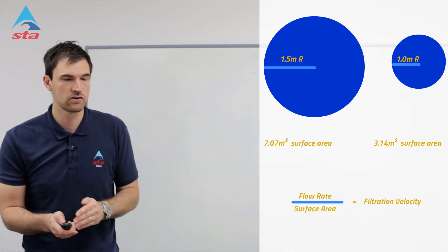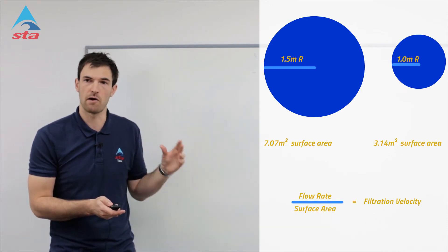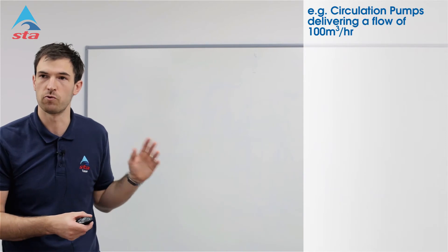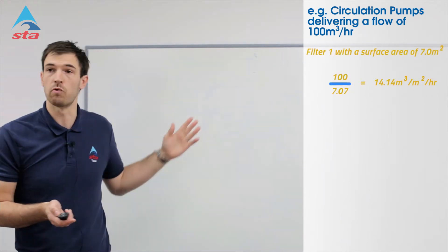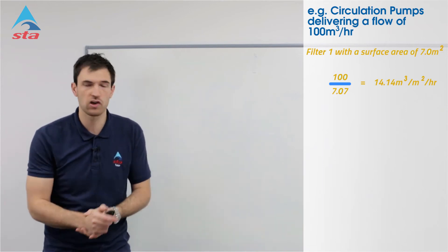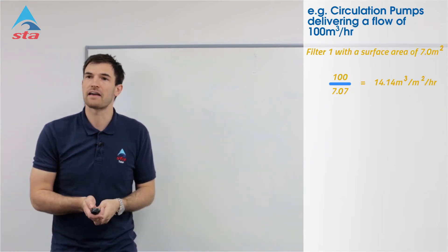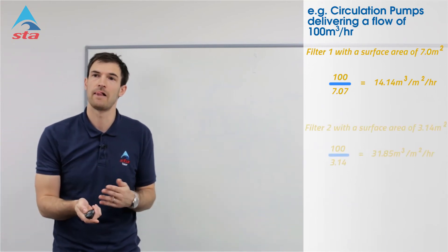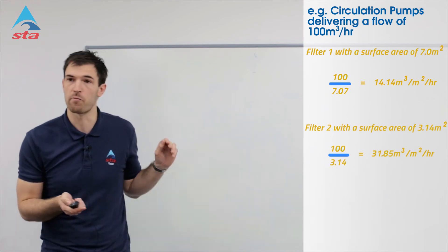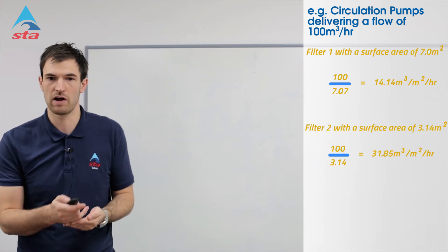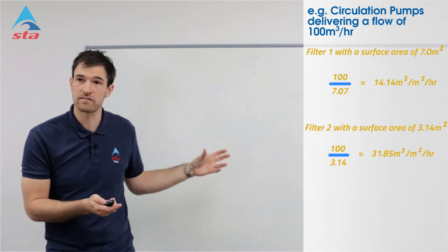Speed is key — the slower the better. Let's take a worked example. Our circulation pumps deliver 100 cubic metres of water per hour — that's the flow rate coming through the pipework. Entering filter one, which has a surface area of 7.07 m²: 100 ÷ 7.07 gives us 14.14 m³/m²/hr — that's the velocity, the speed. Taking filter two with a surface area of 3.14 m², putting that into exactly the same equation gives us 31.85 m³/m²/hr. So that's going a lot faster than the other filter.